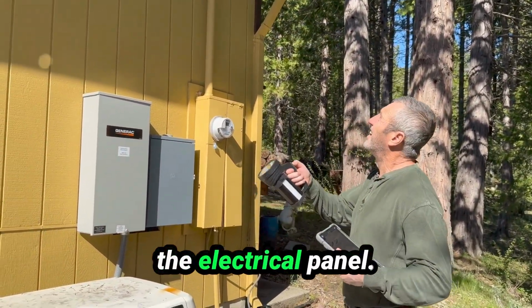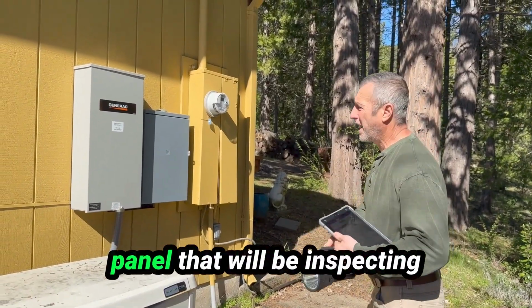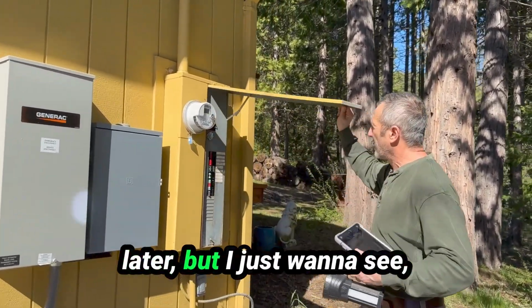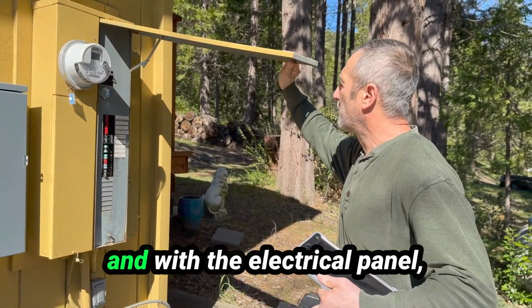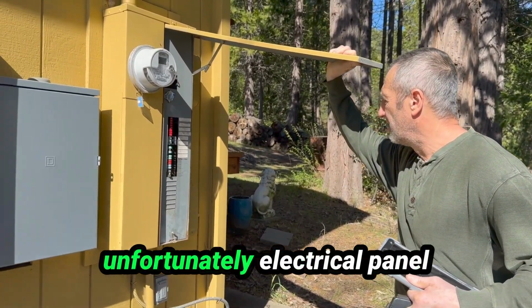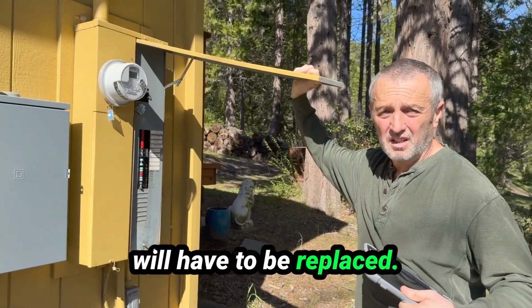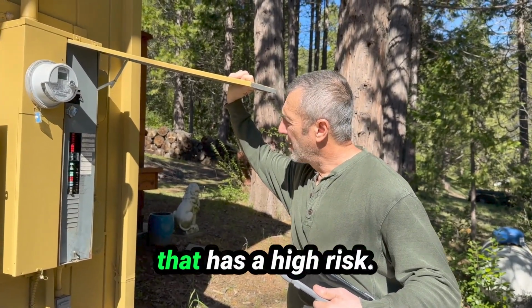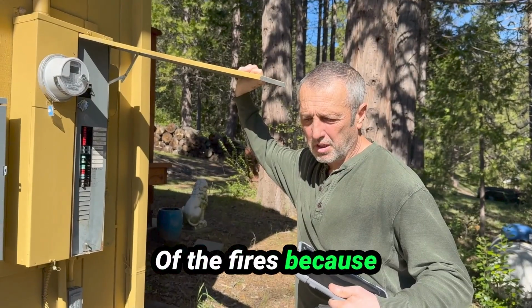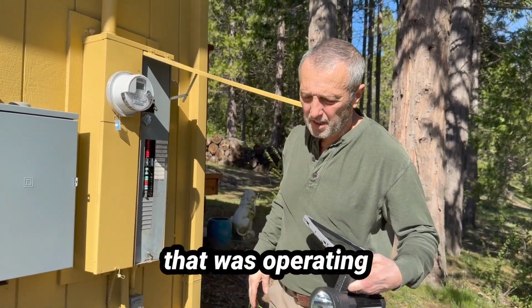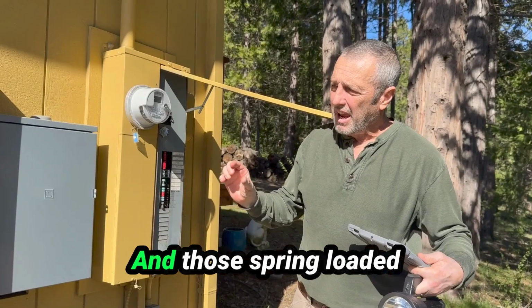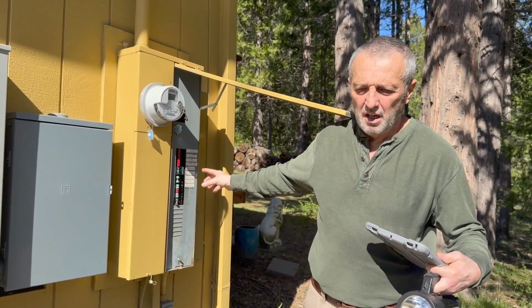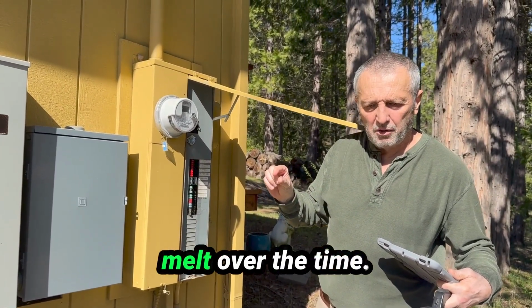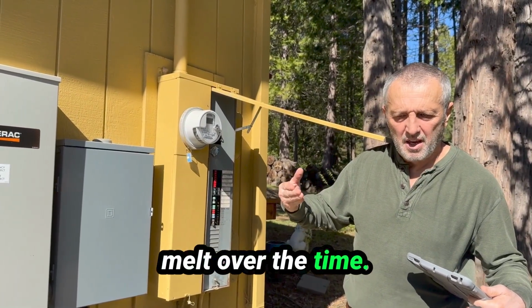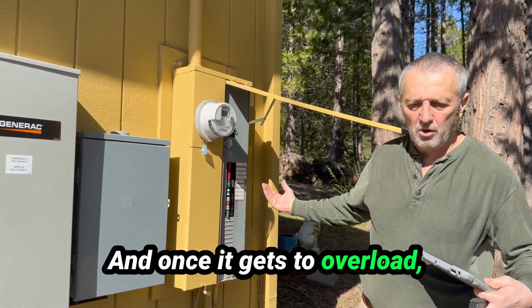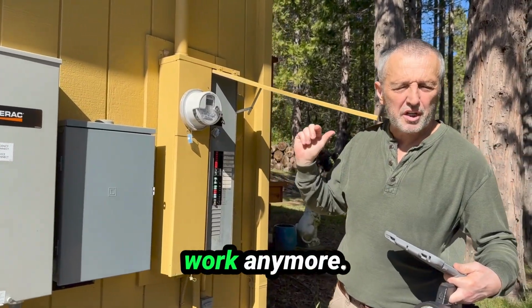Now we have the electrical panel. We'll be inspecting it later, but I just want to note — unfortunately, the electrical panel will have to be replaced. It's a Sylvania GTE panel with a high risk of fire because the breakers are made by the Zinsco company, which was operating back in the 70s. Those spring-loaded breakers actually melt over time, and once it gets to overload and is supposed to trip, the spring doesn't work anymore.